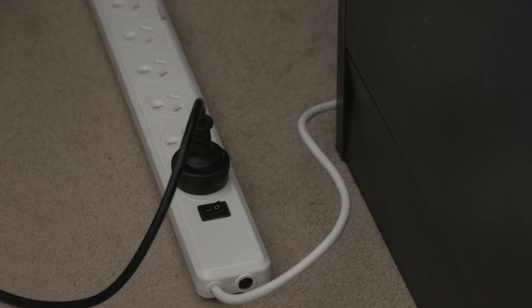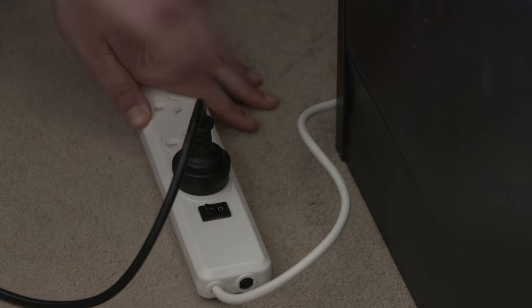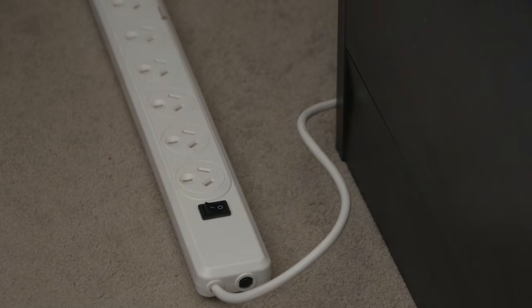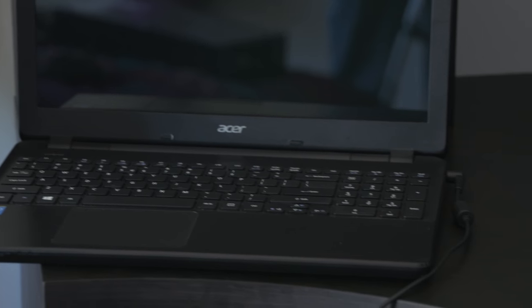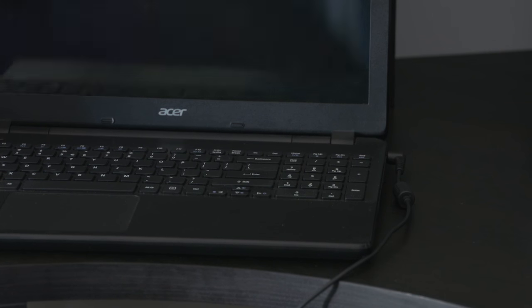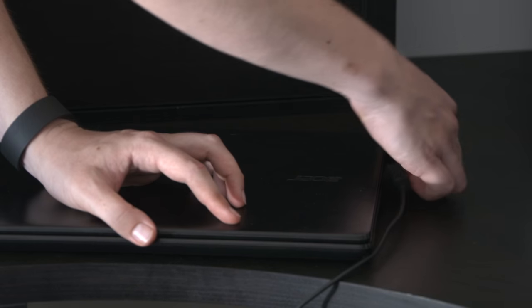The process commonly referred to as testing and tagging, or PAT testing, is the testing of electrical appliances to ensure they meet Australian standards. As when testing any appliance, make sure the power point is turned off and unplugged. Today, I'll be demonstrating how to test and tag a laptop charger. Once disconnected from the power point, ensure it's also disconnected from the side of the laptop.